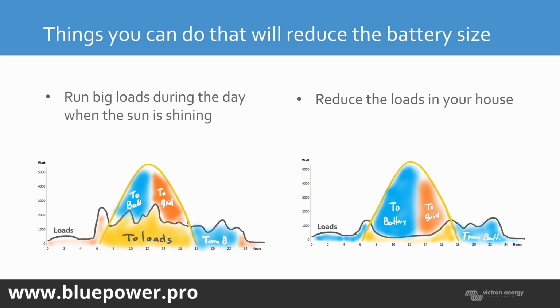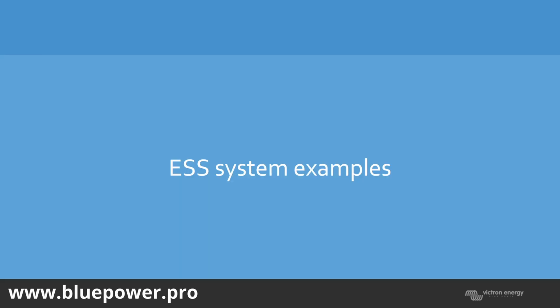So if you size your system correctly, you can have it so that your excess PV gets stored in your battery, and your battery will feed your loads throughout the night. Following morning, you've still got sufficient capacity in the battery to take you through if you've got a little bit of overcast weather in the morning, and then recover the battery charge with solar if available. Next slide. So here's some examples.